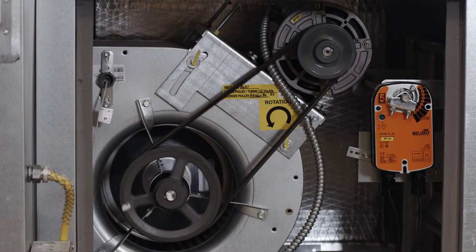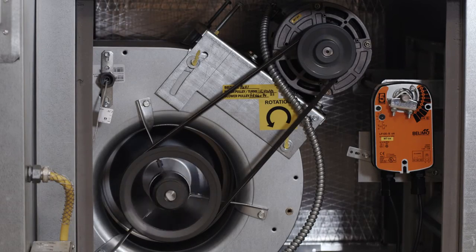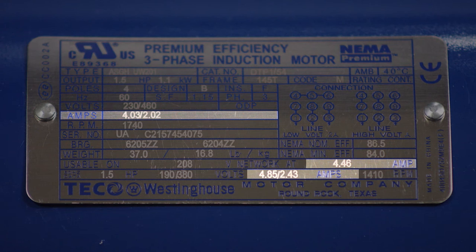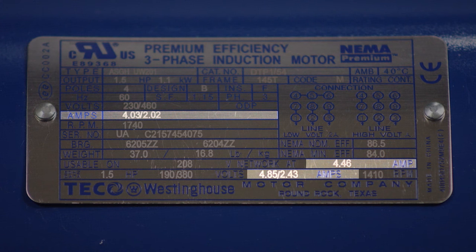Once the blower starts, verify its rotation and ensure the motor amp draw is not exceeding the full load amperage of the motor.